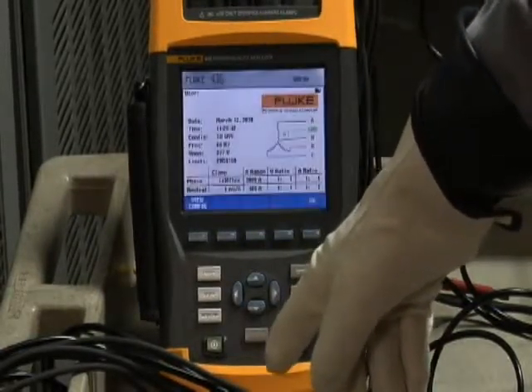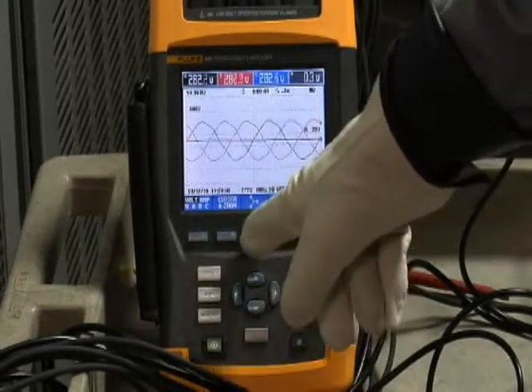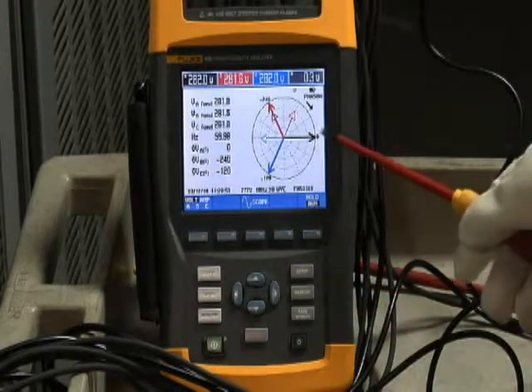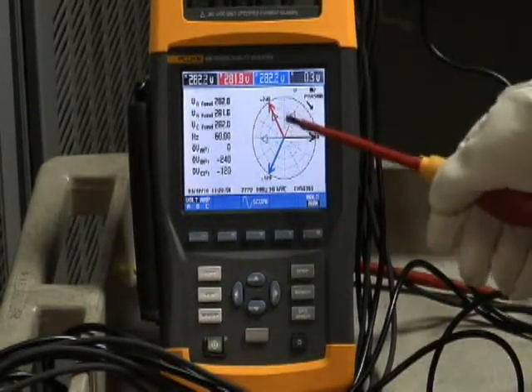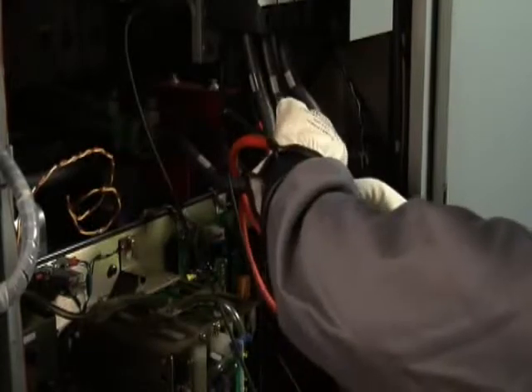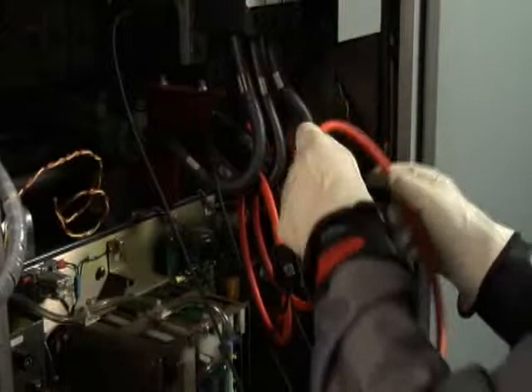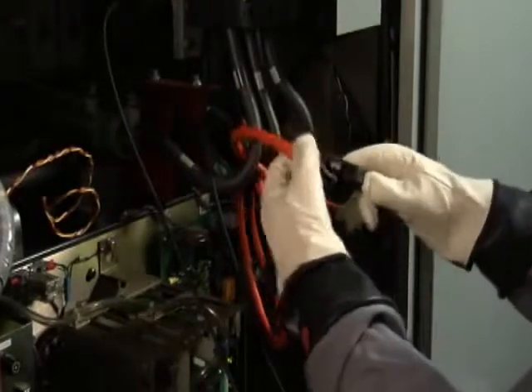Now it's time to put that checklist to good use. An easy way to check your connections is to go to the phasor diagram on your analyzer. If phase A voltage is very much out of phase with the phase A current, that's a connection problem. Sure enough, going back and looking at the equipment, we find that the arrow was pointing in the wrong direction for phase A. Carefully reverse that current clamp, making sure the arrow is now pointing towards the load. That should give us proper voltage and current relationships on the phasor diagram, which we can recheck.